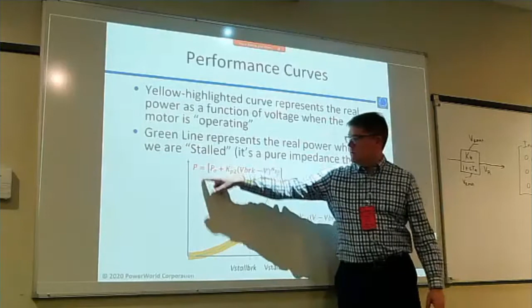However, if you faulted it long enough and at a low enough voltage, the motor would stall and just stay stalled, meaning it's literally just sitting there and not spinning. At that point it just looks like an impedance. Suddenly the voltage recovers, but it doesn't restart - it's just sitting there acting like an impedance. This is bad: when the voltage recovers, the power is going to go way high, oftentimes somewhere around 3 to 4 times higher than where it was operating initially. And it's just going to sit there until it burns something and something trips.